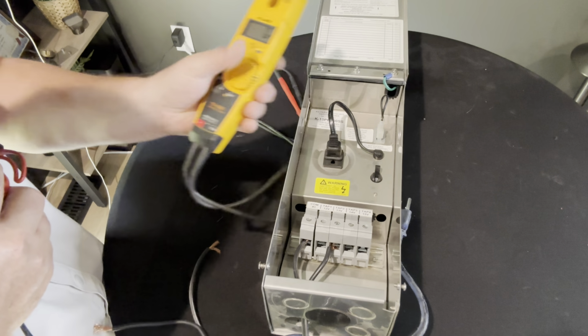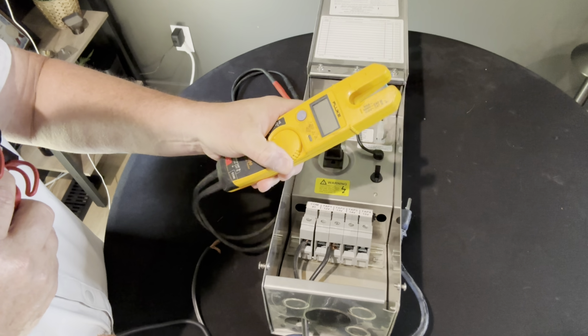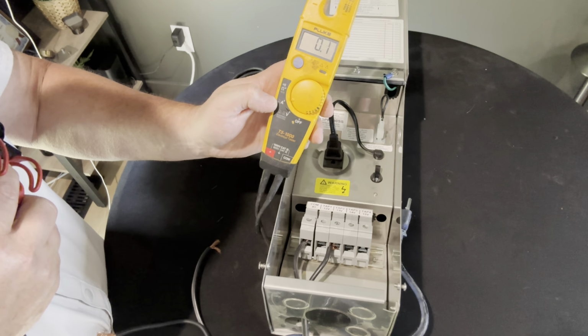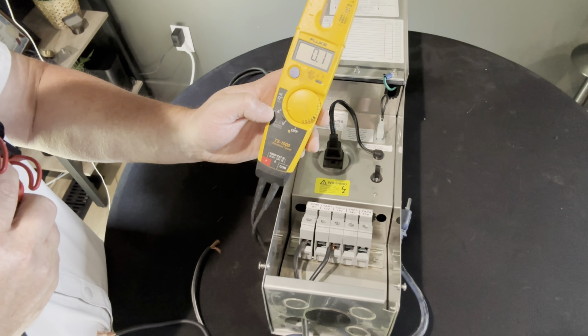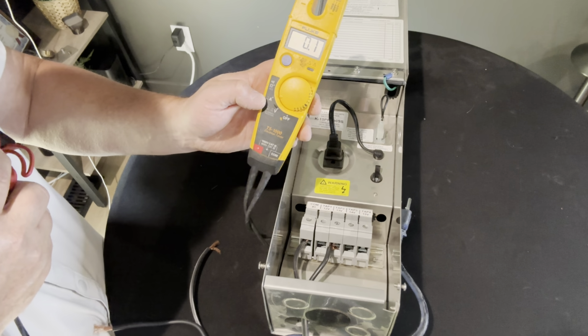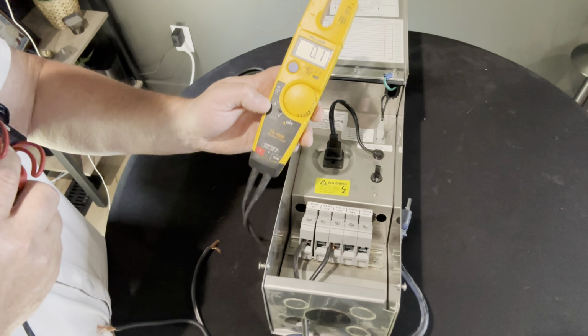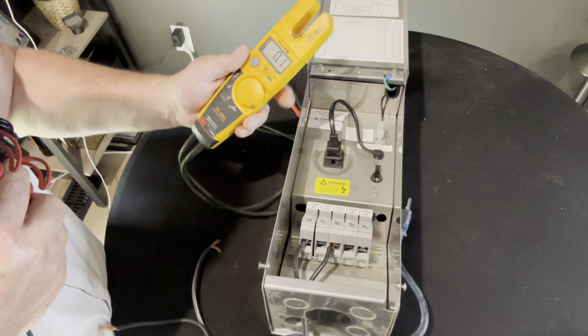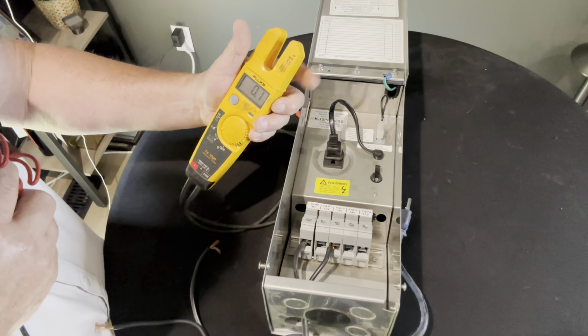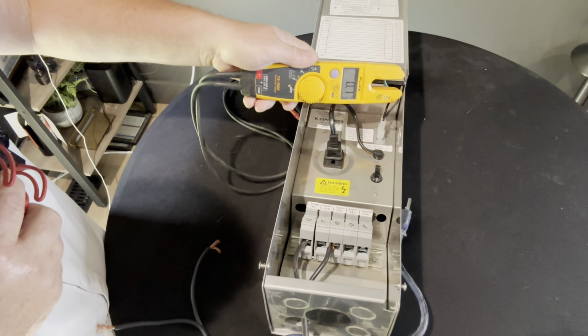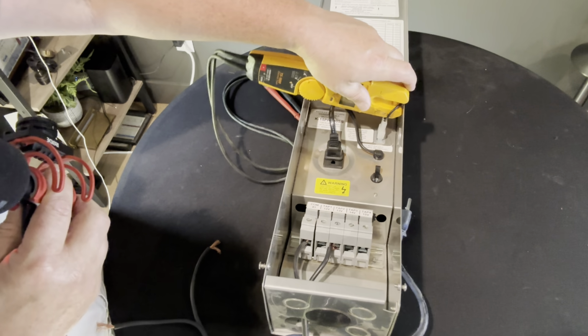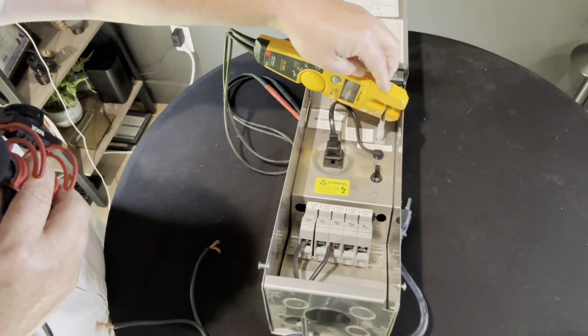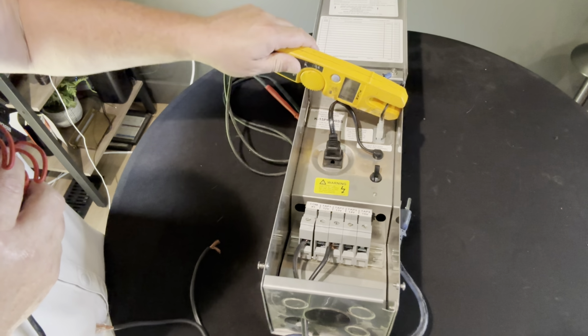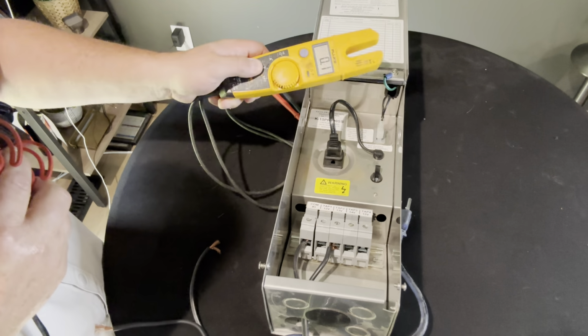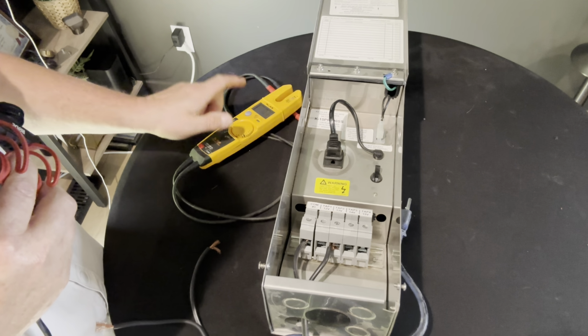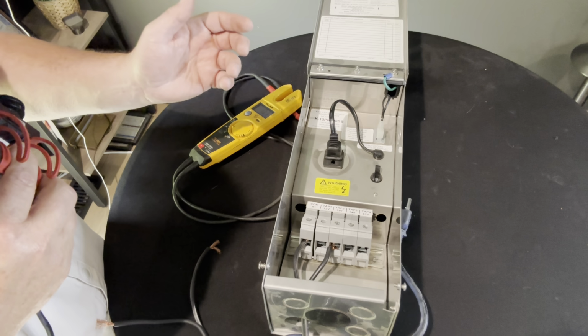So what I would do is take my meter and move it to the amperage setting. If your meter has multiple amperage settings, you want the one with squiggly lines, not straight, because we're testing AC electric. Some meters have a clamp that closes, but this one just has a slot you slide the wire through. If there's a load, that number would show up on the screen. Testing the primary side, it would probably read somewhere between 0.5 and maybe 2.5 at most.